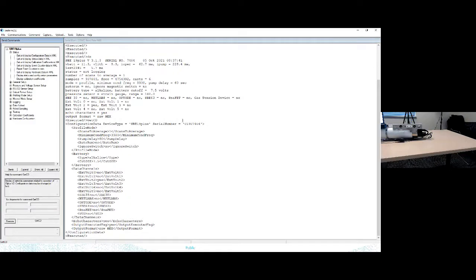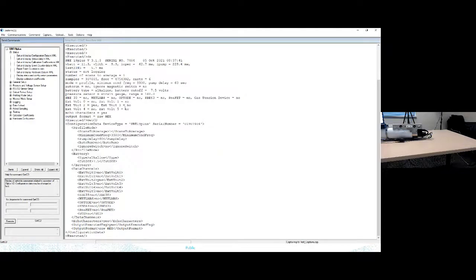Another useful feature in C-Term V2 is the ability to create a capture file. This creates a text file of everything I type into the window and everything the instrument responds with. I highly recommend creating capture files before you deploy this instrument, so you know its configuration before it went out in case you encounter problems. If you ever work with our technical support team, they will often ask you to create a capture file with a specific list of commands in order to get the information they need to troubleshoot your instrument.